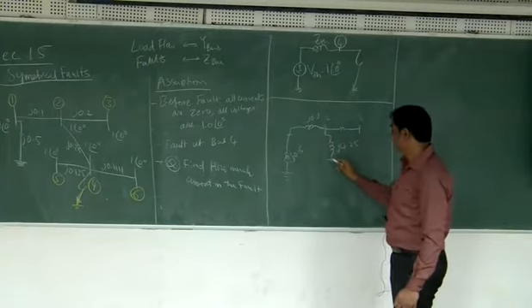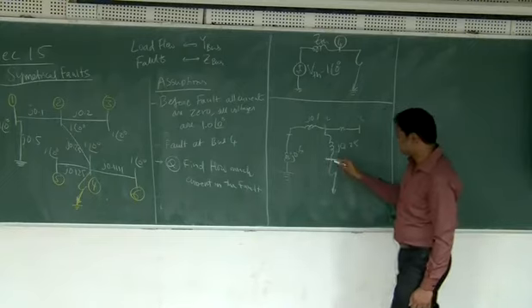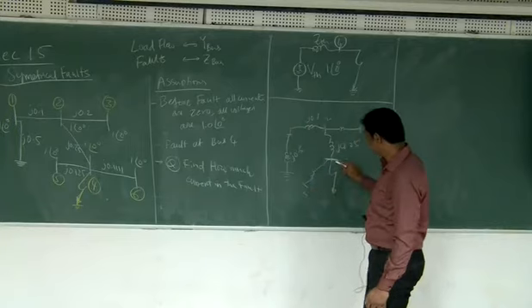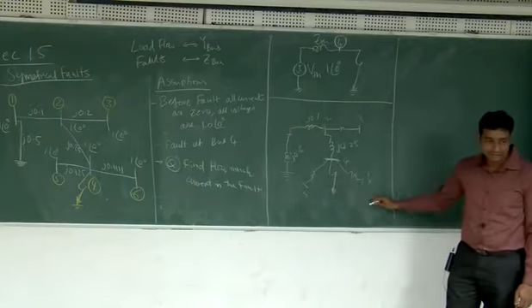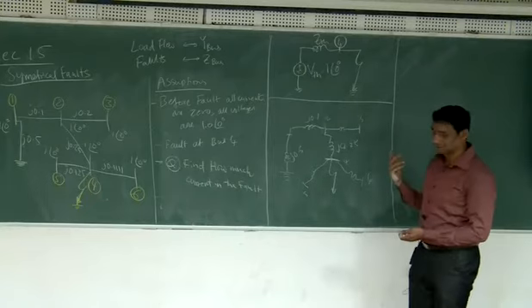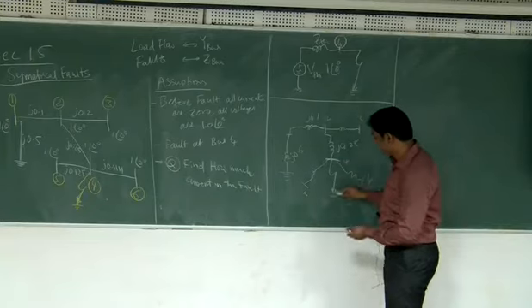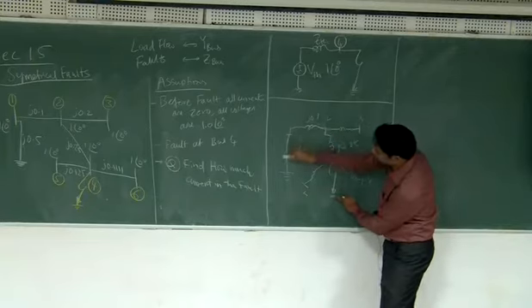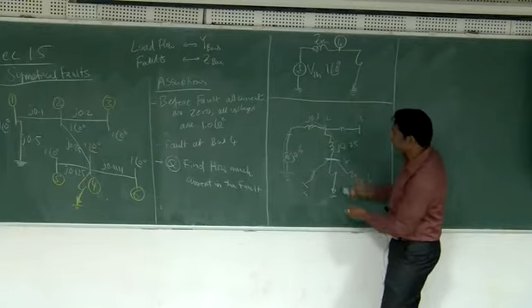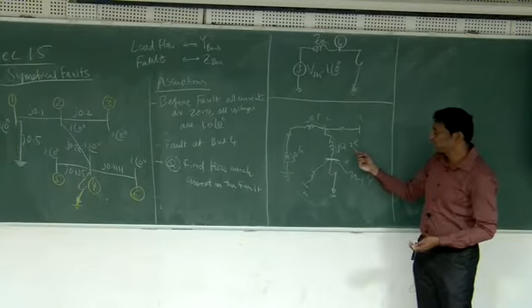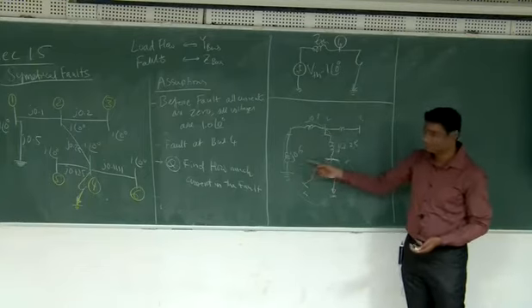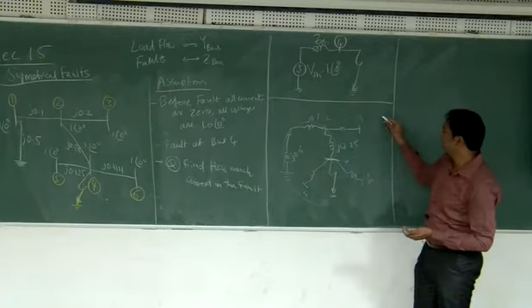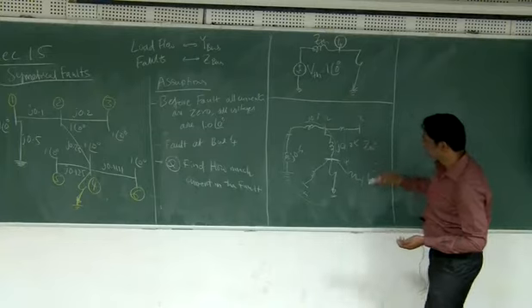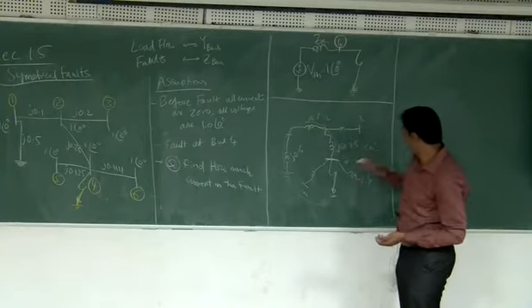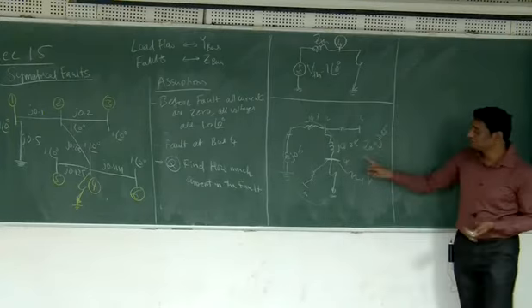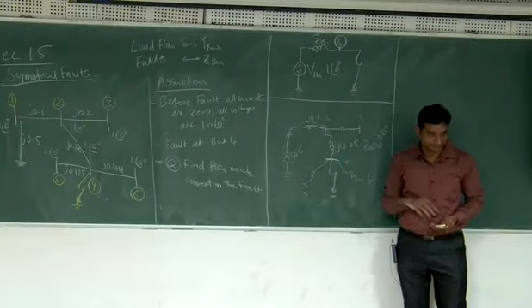Here bus 4 is there. At bus 4 there is a short circuit, and then there is another branch going to bus 5 and another going to bus 6. But since these two are open circuited, I am not interested in them. So for the Thevenin's impedance, if I measure the impedance between these 2 points, I have only this path. What is the Thevenin's impedance? 0.25 series 0.1 series 0.5, the addition of these 3. That will be your ZTH. 0.25 plus 0.1 plus 0.5 is 0.85. So this is your Thevenin's impedance as per the circuit given.